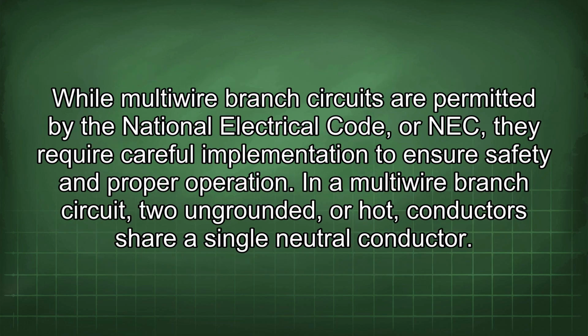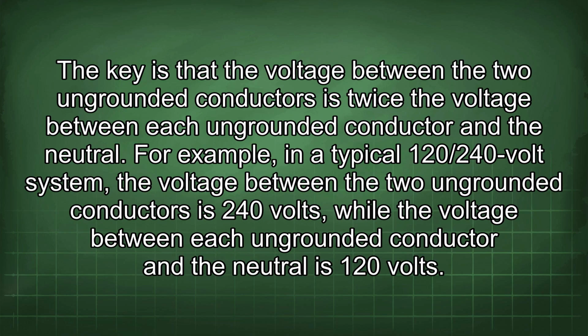While multi-wire branch circuits are permitted by the National Electrical Code, or NEC, they require careful implementation to ensure safety and proper operation. In a multi-wire branch circuit, two ungrounded, or hot, conductors share a single neutral conductor. The key is that the voltage between the two ungrounded conductors is twice the voltage between each ungrounded conductor and the neutral. For example, in a typical 120/240 volt system, the voltage between the two ungrounded conductors is 240 volts, while the voltage between each ungrounded conductor and the neutral is 120 volts.